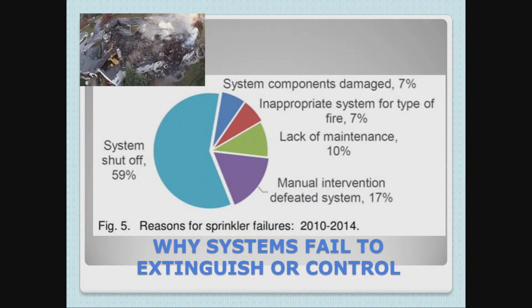What happens historically, 59% of the time that a sprinkler system does not control or extinguish a fire, it's because a valve was off. Another 17% of the time, it's because somebody turned a valve off too soon. They thought the fire was out, they didn't want the water damaged, they turned the valve off, and guess what? The fire came back, and by the time they got the valve back on, it was out of control.